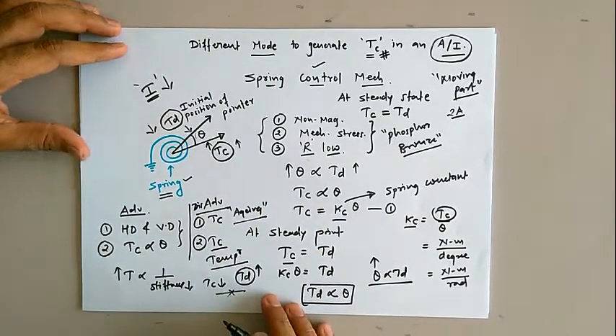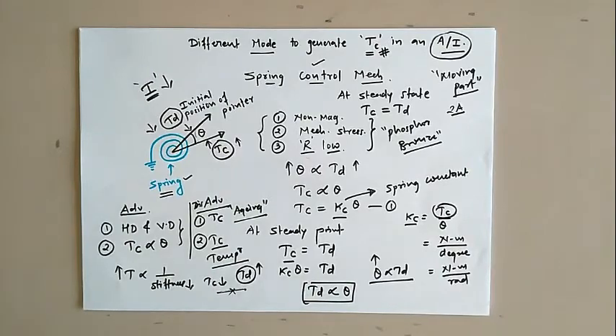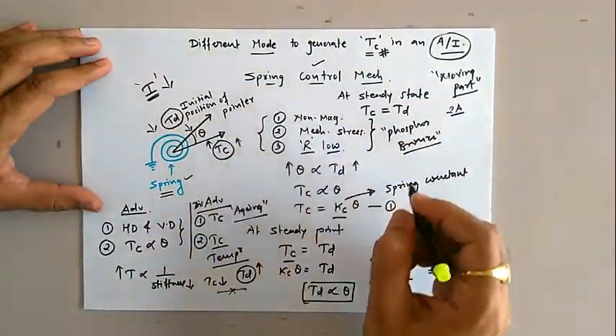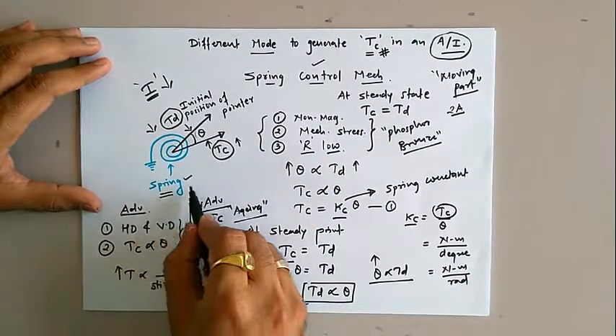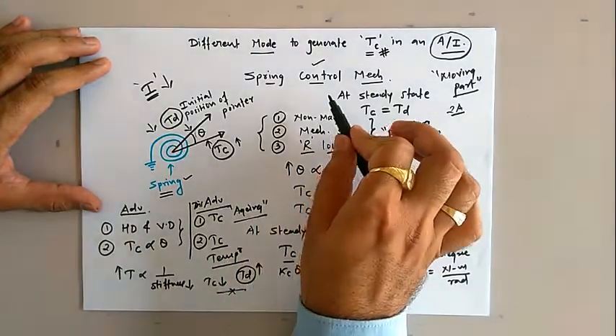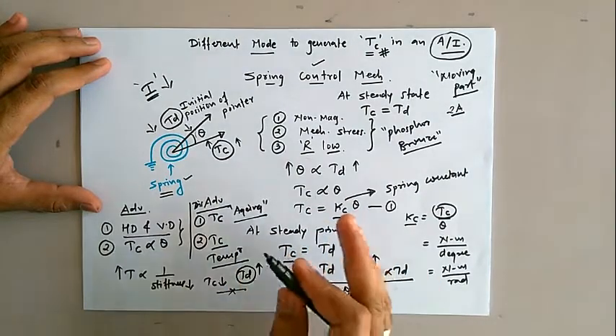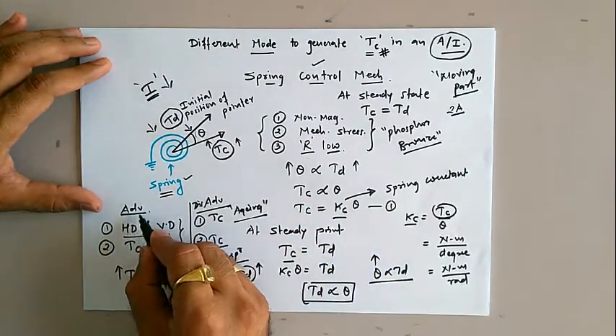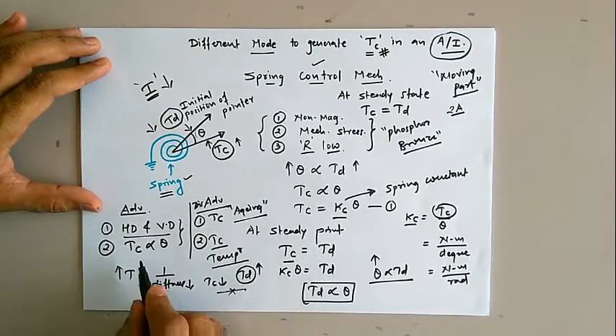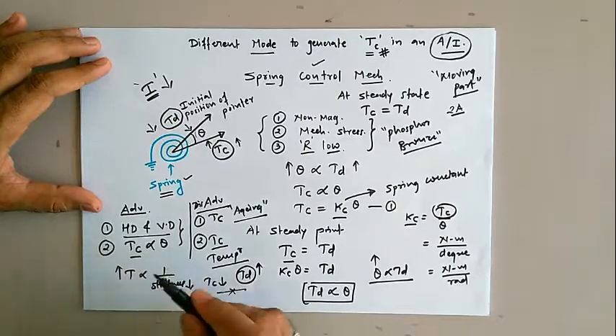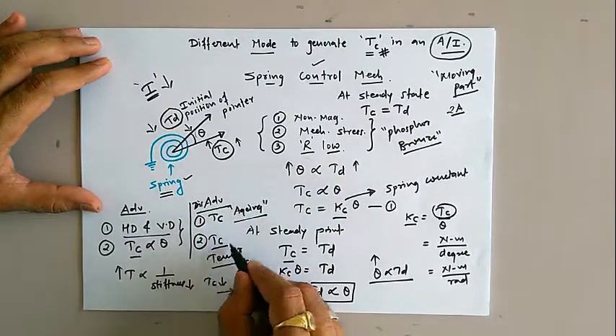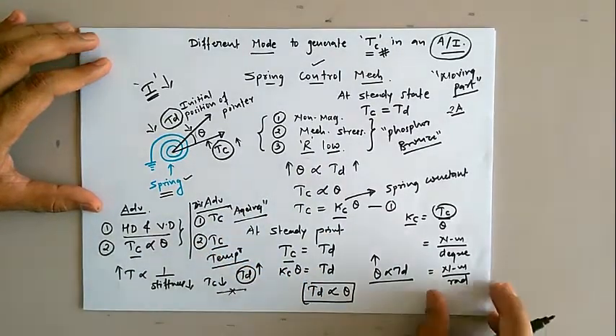To overcome that problem we need to go for gravity control mechanism. Let us summarize spring control: the controlling torque is produced using a spring arrangement. Advantages are it can be used in any position — horizontal or vertical dial setting — and the controlling torque varies linearly with deflection angle theta. Disadvantages are it is affected by aging and by temperature.